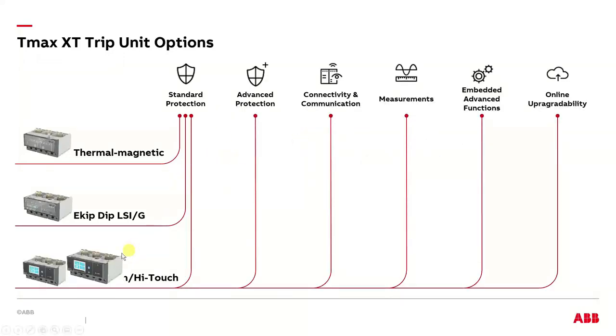So this just shows you our line of trip units that fit in those breakers: thermomagnetic, EKIP Dip, which is a normal solid state trip unit, and then what we call Touch or High Touch, and that's your top of the line advanced solid state trip unit. So you can get standard protection in all of them, but then you get all this other stuff that you can do with the advanced unit. The advanced protections are like your voltages and frequencies and power flows. You can have communications, measurements, embedded functions, PLCs, stuff like that, and you can upgrade it. So that's the big differentiator.